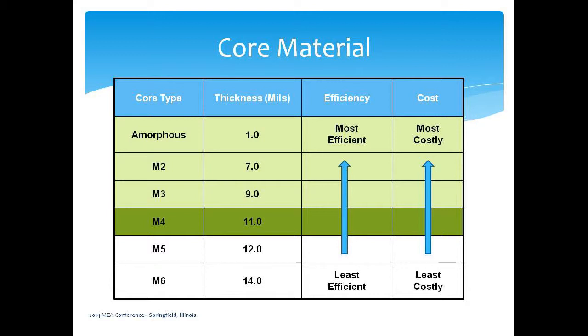This is the slide I alluded to before on the different grades of core steel. This is looking at silicon core steel - grain-oriented core steel designed to be very low loss. You have to anneal it after you form it, so it's not your typical tank steel or production steel. Domestically, AK and Allegheny are the two suppliers of it, and for amorphous material, Metglas is the supplier.